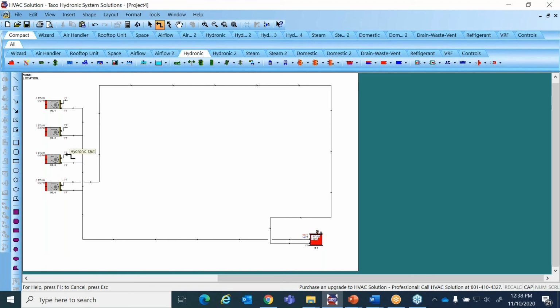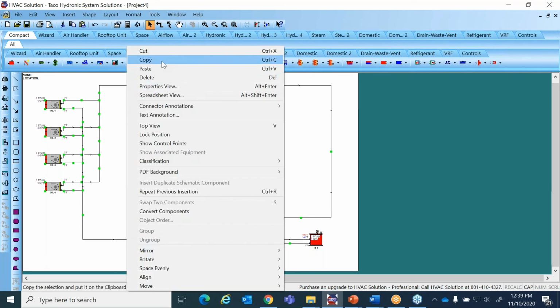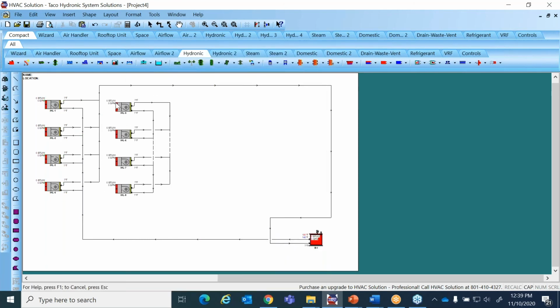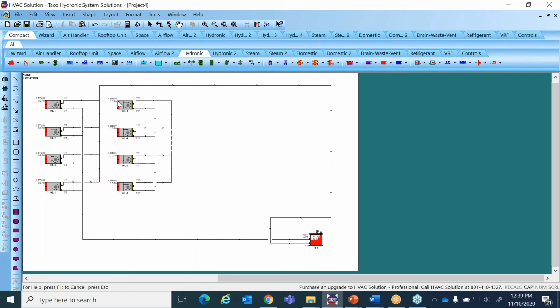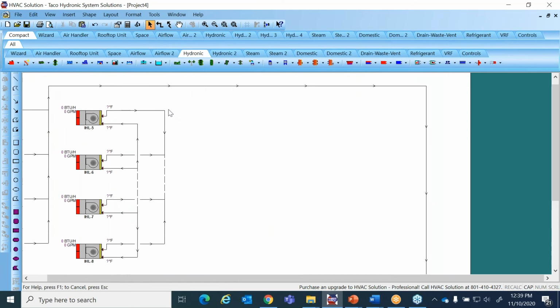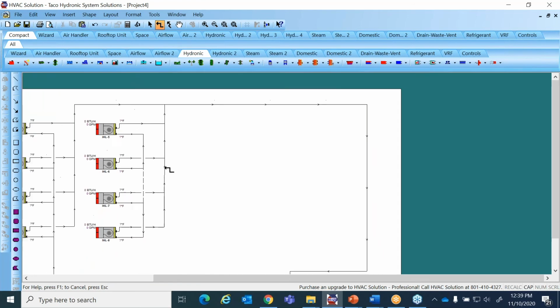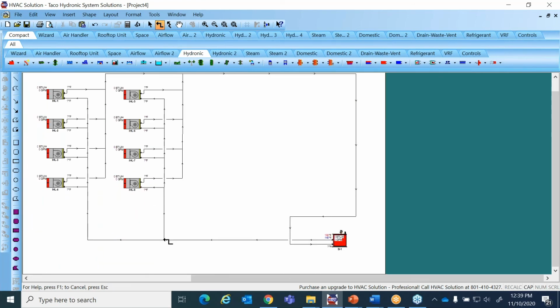We get this question every once in a while, and it's a great question. But see that I wasn't careful enough—I didn't get all the way out to the piping. You need to be careful, and honestly, you need to be a well-trained HVAC engineer to use this software. I say that because it doesn't tell you when you do something wrong. So say you put the expansion tank on the discharge side of a pump instead of the suction side—it's not going to warn you that that's not the best location. You need that knowledge to get the full benefit of this software package.